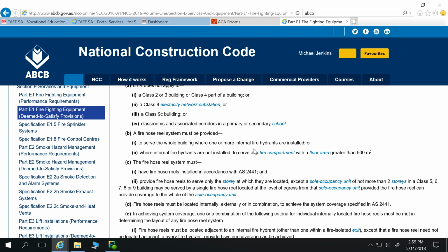Okay, how long is a fire hose? Because if we've got approximately 400 square metres of floor area, over a distance of almost 40 metres there, well, a bit over 40 metres, what if a fire hose is only 10 metres long? Then we're going to have four fire hoses about the place in the building.